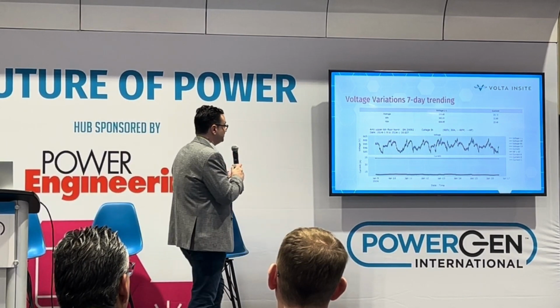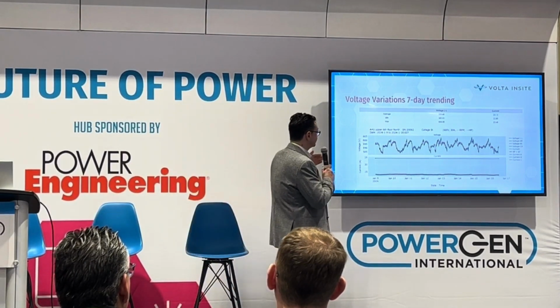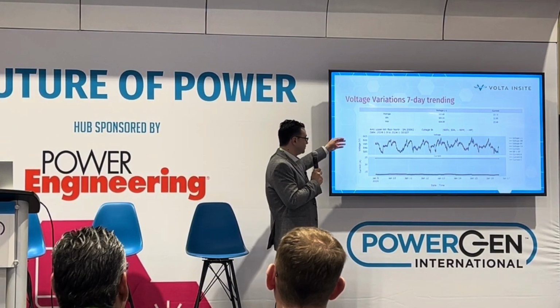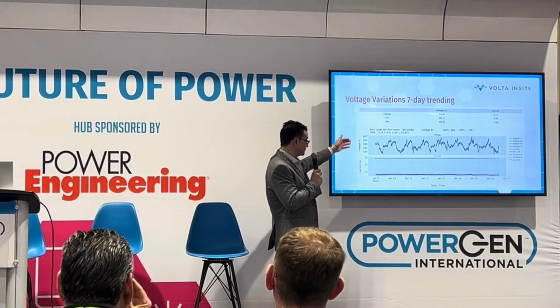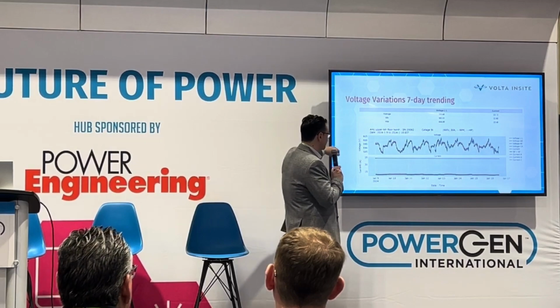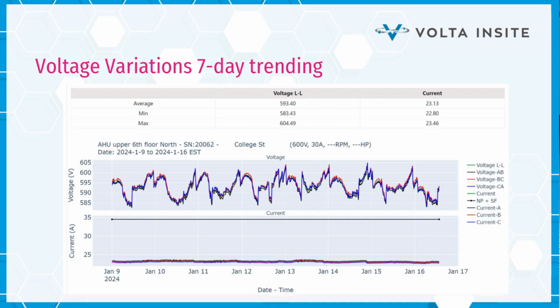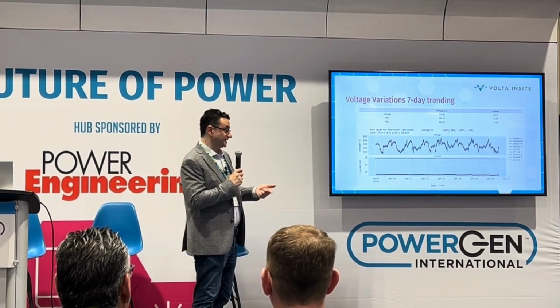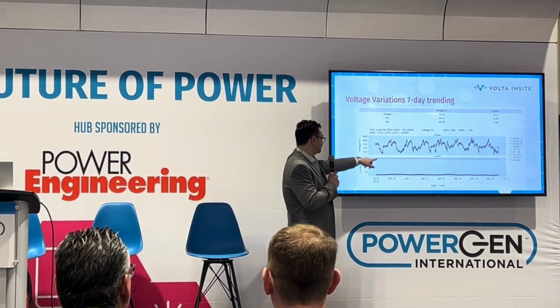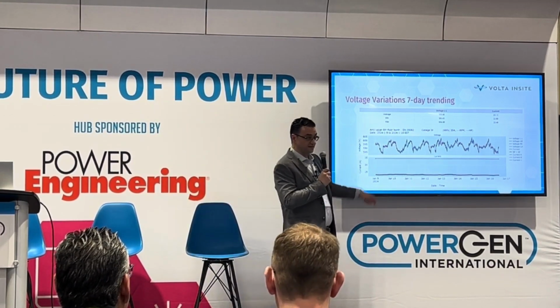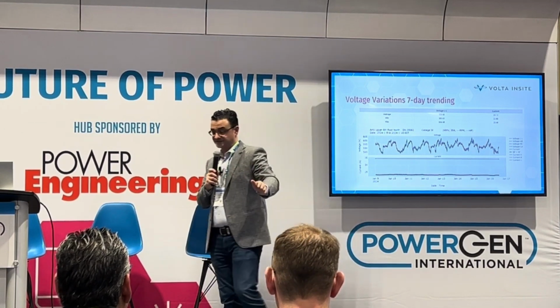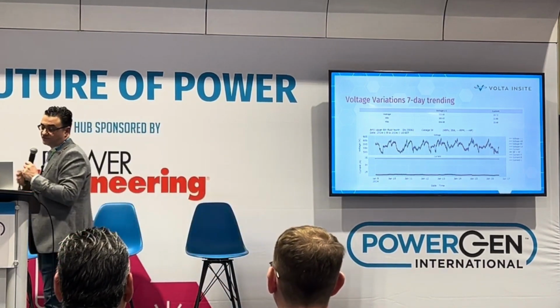Additionally, this is an example of voltage variations over a 7-day trend. So again, this is from Canada. This is from the Toronto region. This is not too bad, but our nominal voltage should be at 600 volts. And you're noticing all the sample points, they're at 595. And at some point during the day, because of loading, so it could be a consequence of loading within the facility itself, as well as utility draw, we're reaching levels of about 583, 580 volts. Not a major problem, but this is an example of the amount of voltage variation.